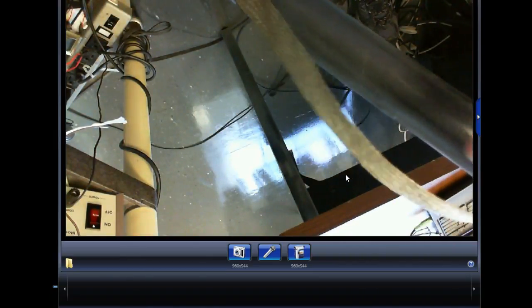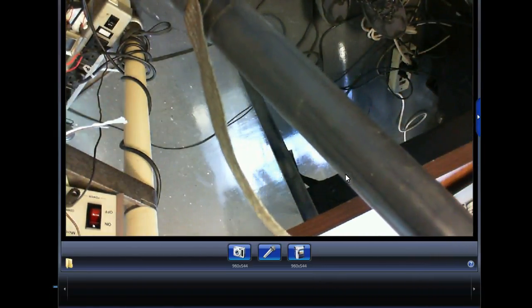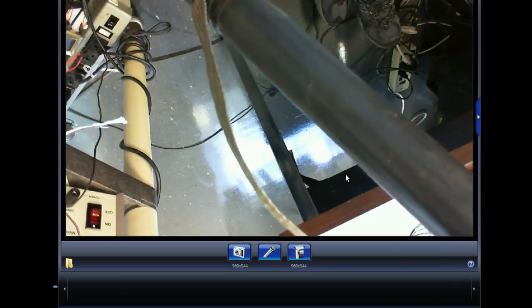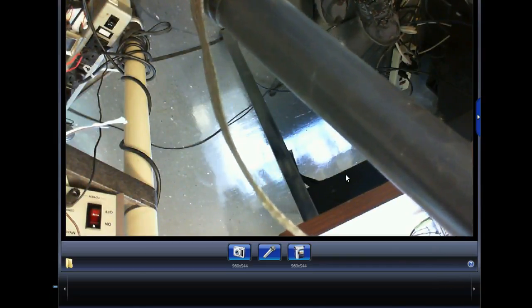But when we terminate this, or when we splice it, we've got to maintain all those layers. Does that make sense? We've got to maintain the semiconductor layer, the insulator layer, the second semiconductor layer, and the shield, right? You'll understand that. If we don't do that, then what happens? Then the cables break down. And you don't want these suckers to break down.